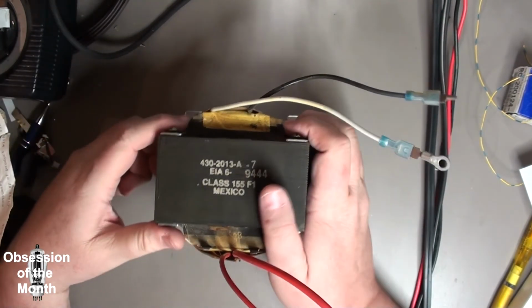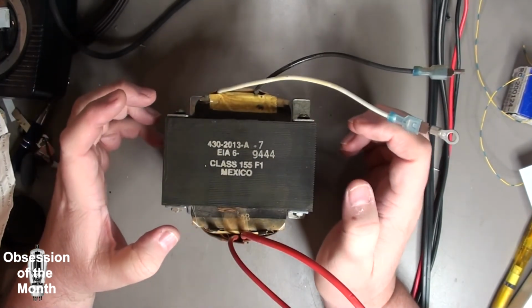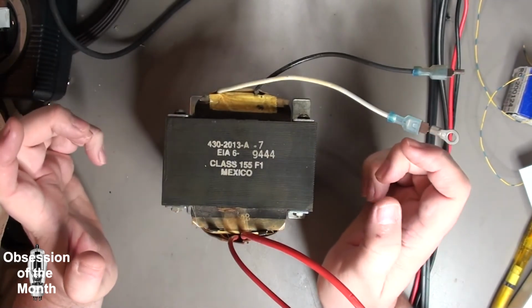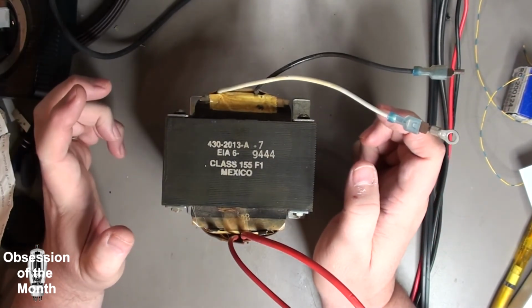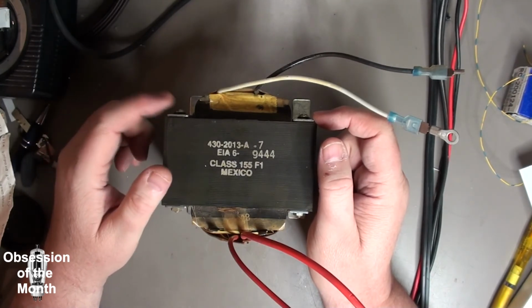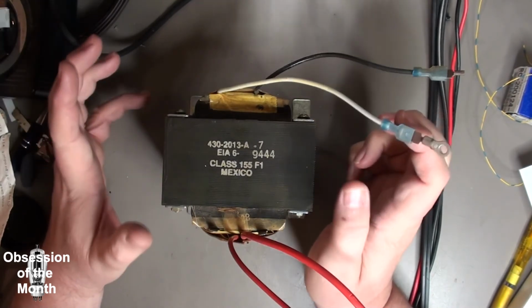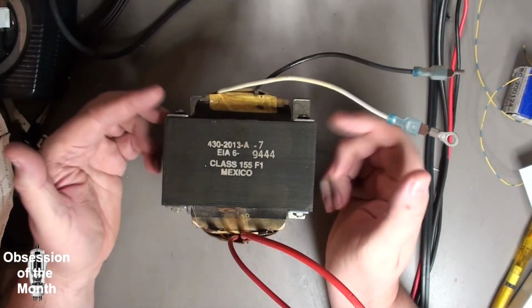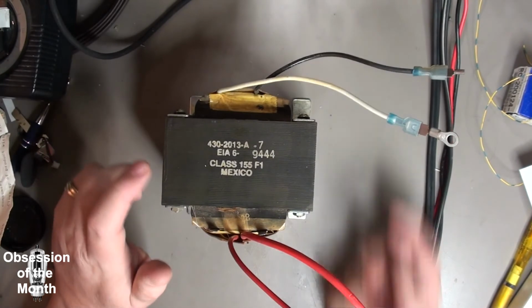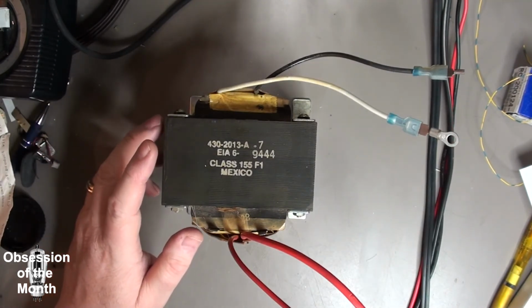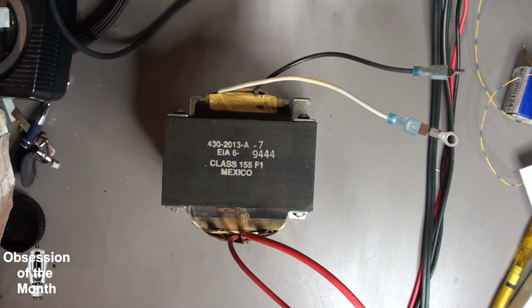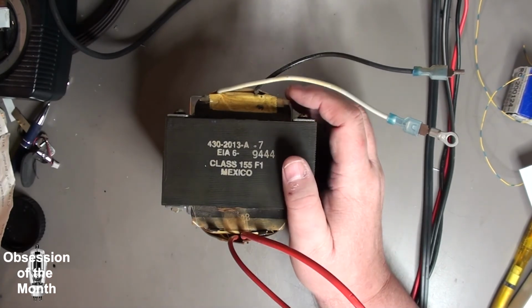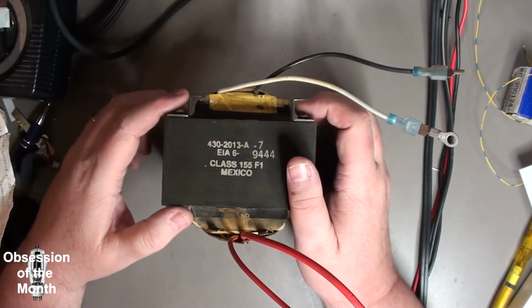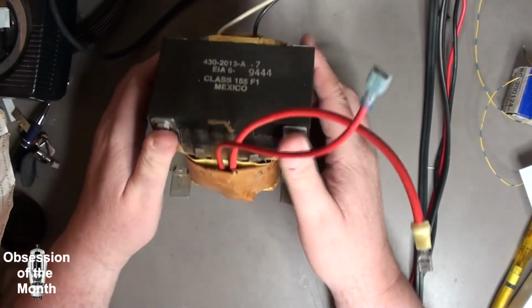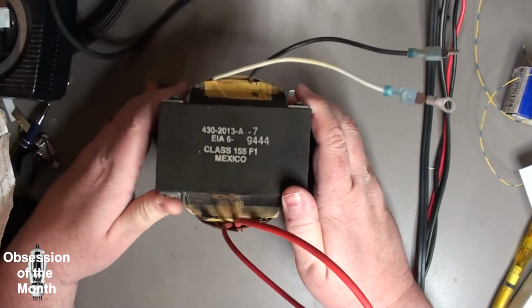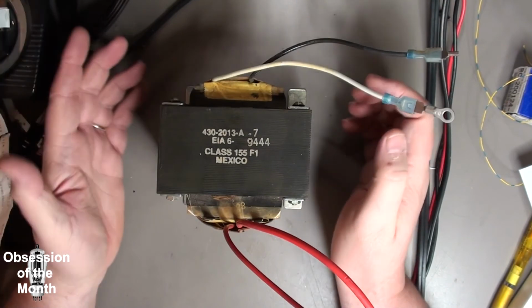But how do you determine what the amp rating is for a transformer? If you know the rating from, say, a UPS it came out of, you can discern it from that. Like if this was a 1200 VA unit, about 1200 watts, then based on the 61 volts you could get out of it, that means it's rated for 19 amps.